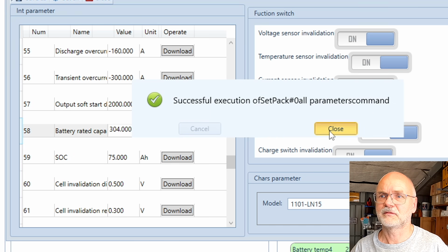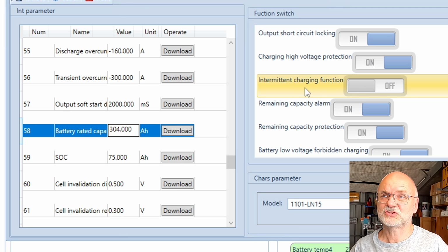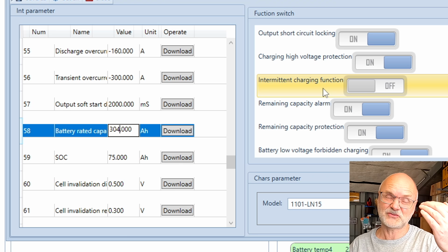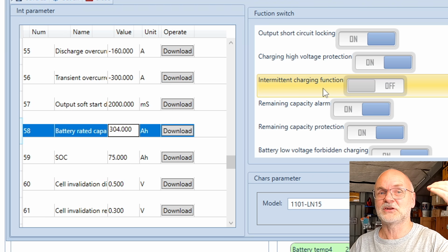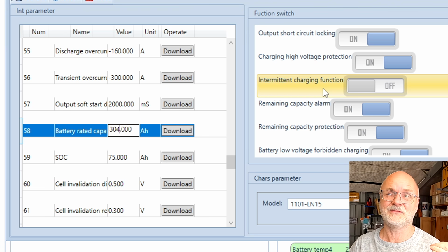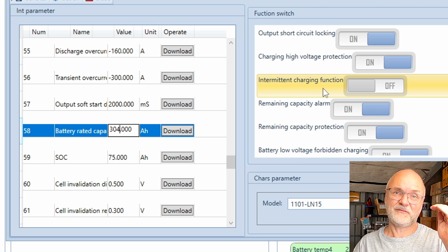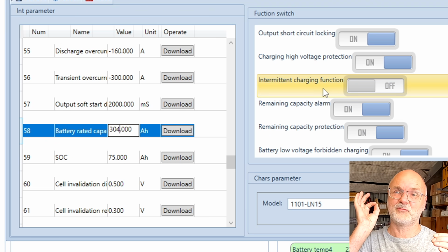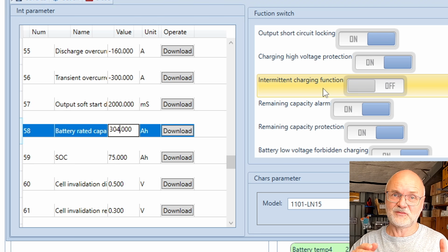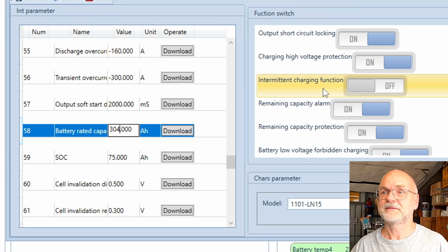Set. All right, I've also turned off the intermittent charging function, because this means once the battery is fully charged, it will turn off your charge MOSFETs and won't turn them on again until we hit 96% state of charge. So it discharges the battery by 4% and then recharges to 100%, down by 4%, and so on. This is because we want to stay at 55.2 volts, give the balancer time to balance the battery pack, and then the solar charge controller will go into float mode at some stage, 53.6 volts, and keep the batteries fully charged at a lower voltage. But I don't need this functionality here.